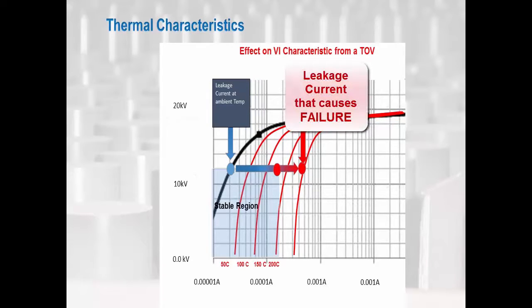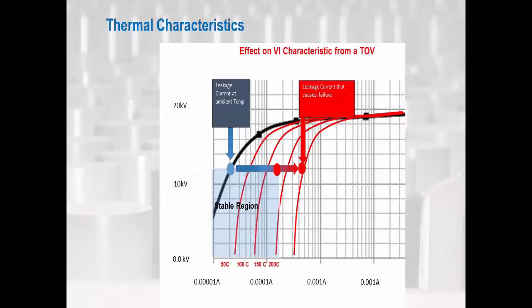If the thermal coefficient of a disk is not the same as it was during the design tests, the temperature of the disk could be pushed into an unstable mode of operation. If this happens, the disk continues to increase in temperature even after the transient event has ended. A thermal runaway occurs and the arrestor fails. Testing the thermal stability of a disk before they are installed in an arrestor guarantees the arrestor's thermal performance in the field. Good quality disk suppliers will have a variation of this test run periodically to ensure TOV performance.